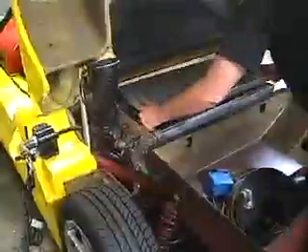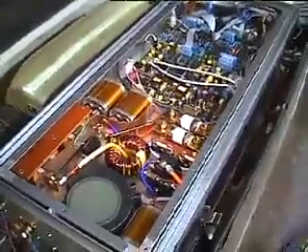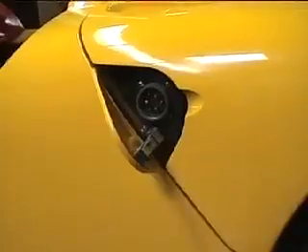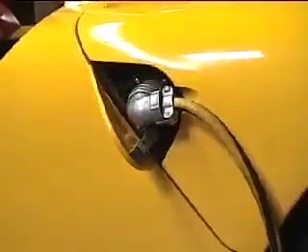The vehicle power electronics unit handles all the two-way power control. It is connected to a standard high-current 208-volt circuit in the building. This 80-amp connection allows 16 kilowatts of power to flow in either direction. In homes, power flow would typically be limited to 7 kilowatts.